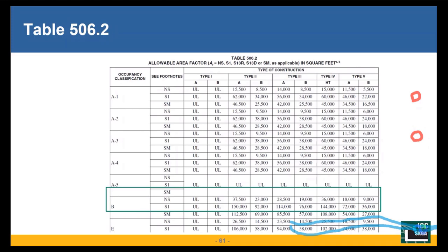And of course, the state fire marshal regulated occupancy will show that you cannot get a story increase. So the state fire marshal regulated occupancy in this table did not take advantage of the story or height increase. It's only taking advantage of the allowable area increase using sprinkler system and multi-story. So again, this table represents the pure area factor taken earlier from that table, and the allowable area increase for sprinkler and number of stories is already built in.